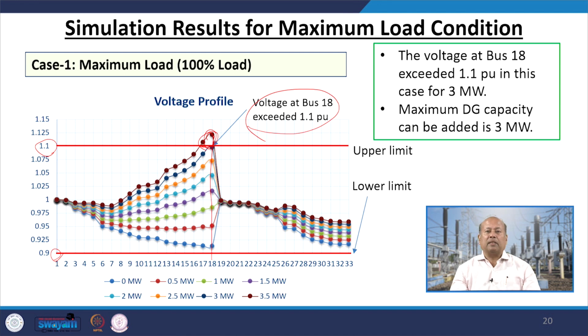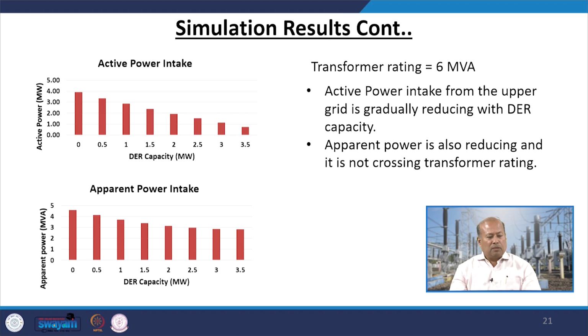So, the maximum DG capacity that can be added is 3 megawatt. That means the moment you inject more than 3 megawatt, the voltage violation occurs, and hence we recommend that the hosting capacity for the network for DG integration of PV will be equal to or less than 3 megawatt. Is it clear? Now, these are the simulation results: active power intake, apparent power intake, and the transformer rating of 6 MVA. Active power intake from the upper grid is gradually reducing with DER capacity. Apparent power is also reducing and it is not crossing transformer ratings.